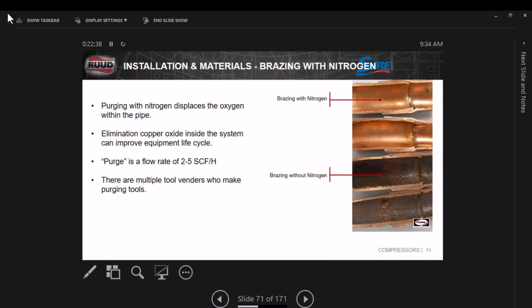So when you go to change that compressor out, because the compressor failed, because the expansion valve failed, slugging the compressor, so we had a chain reaction there, right? And it's all due to this stuff right here. So we braze with about a half a psi of nitrogen through the line. Free flow through the line as you're brazing. It's an inert gas. It won't let the stuff in there oxidize.